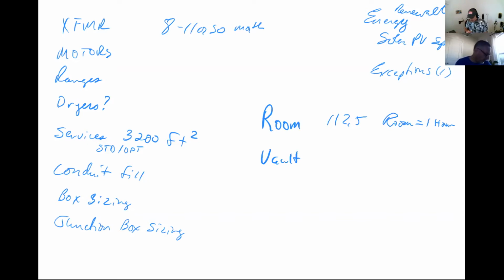Now there are some rules for transformer vaults. If you get over to page 337 under Part 3, 450.42 and 43 deal with the vaults - the thickness of the concrete, the height of the sill to keep liquid from flowing out of the vault area, things of that nature. The vault ratings are a 3-hour rating all the way around. So anything like bus bars penetrating the back of it coming from the utility side, those have to be in a 3-hour rated case assembly. 3 hours is what we use for any kind of vaults, and that's really the huge difference between the two.